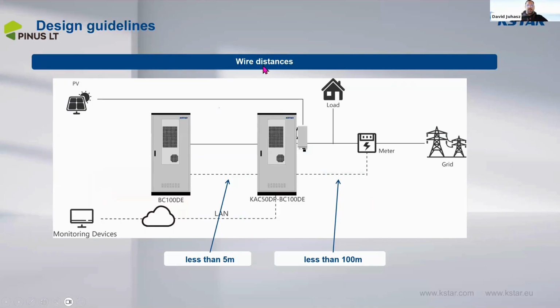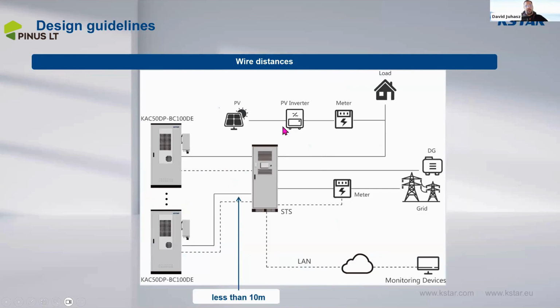We have some limitations in the wire distances. If we are putting two cabinets next to each other, the distance should be less than 5 meters. And regarding the meter, it's a simple RS485 communication between the master cabinet, which should be less than 100 meters. The next is the STS solution. If we are using the old cabinets with the STS, they shouldn't have more distance than 10 meters, because we have special communication cables that we give with the equipment. So this 10 meters is necessary to keep if we are using STS. It's one thing to check.